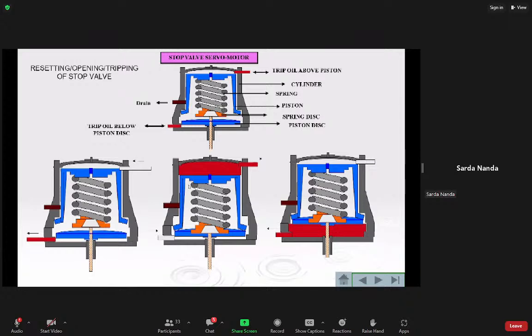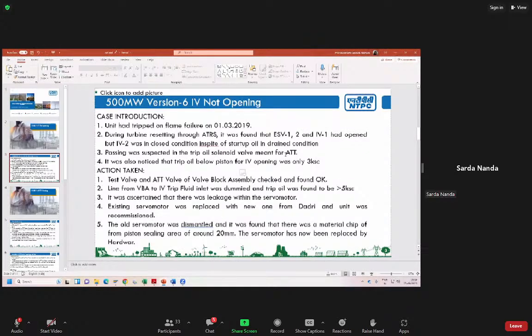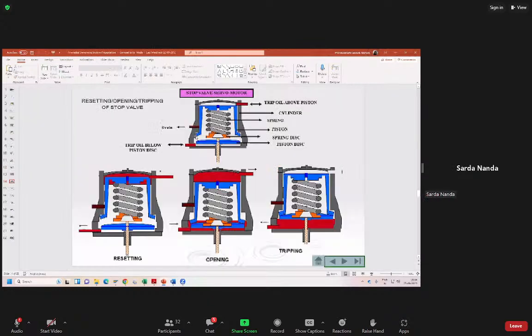So we tried several things, but it did not happen. We found out that there's a problem in the servo motor itself, and so we replaced the servo motor. We got a spare servo motor from Dadri, and we replaced it. The unit was also recommissioned. When we dismantled the servo motor, it was found that there was a material chip. There was a small piece of material that was chipped off from this piston.